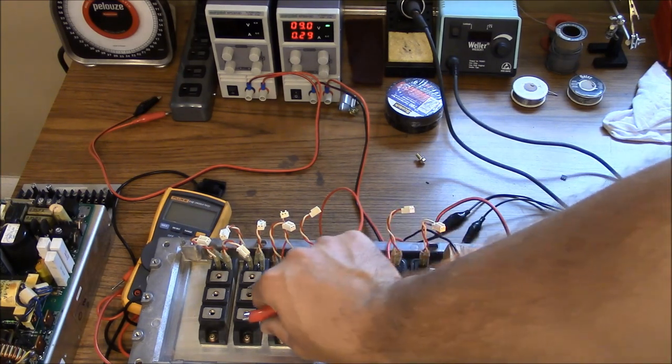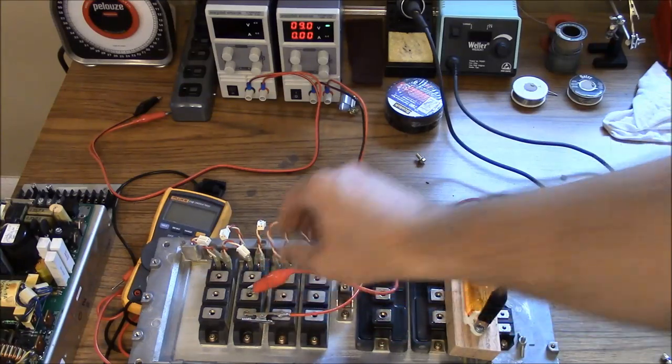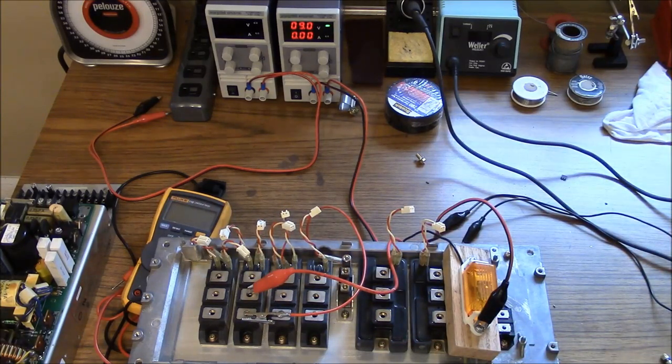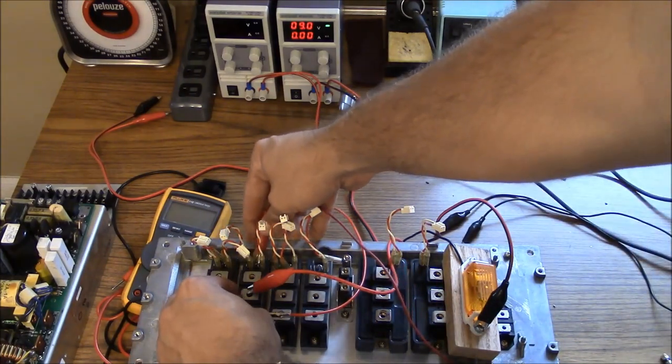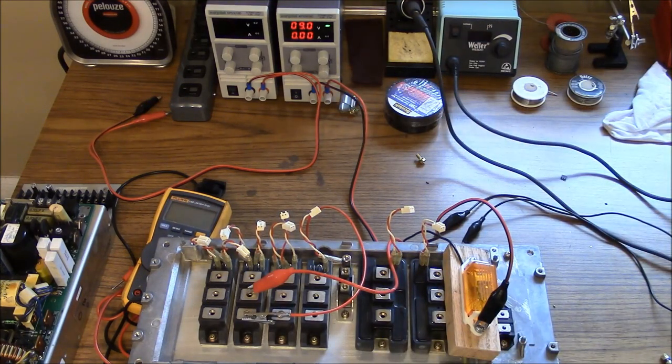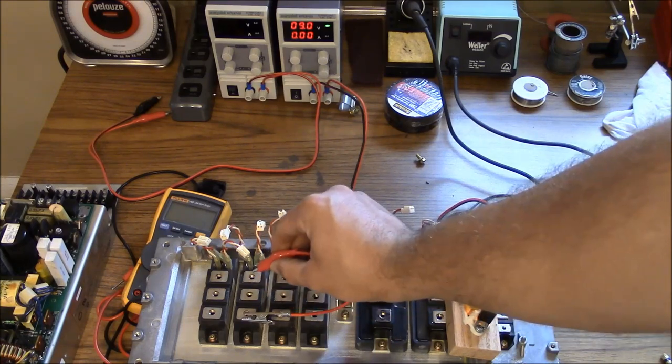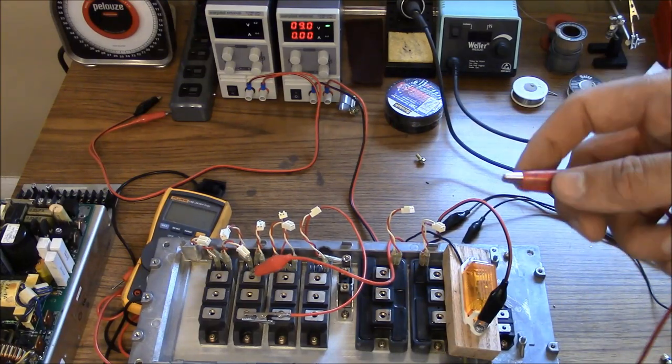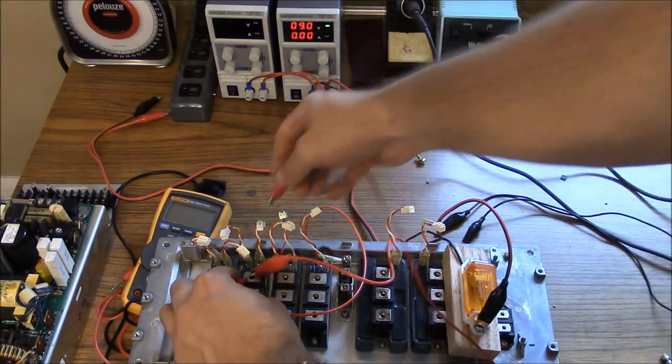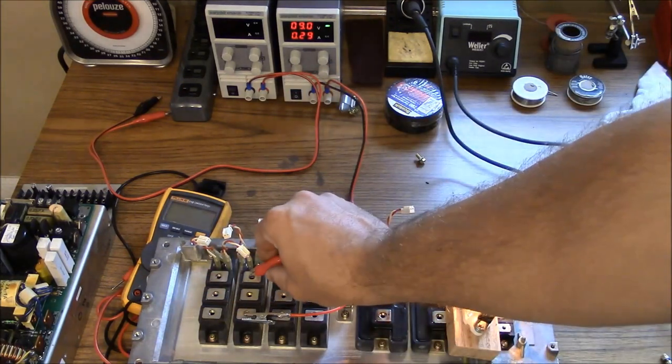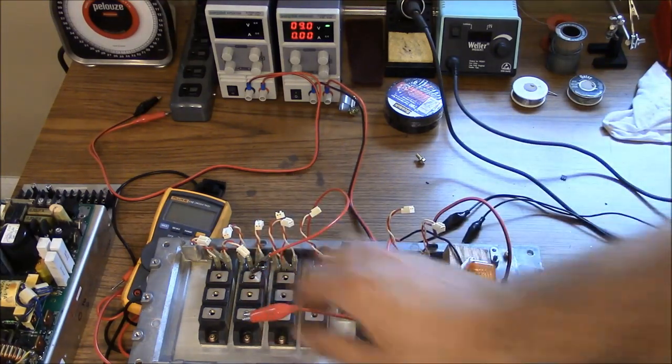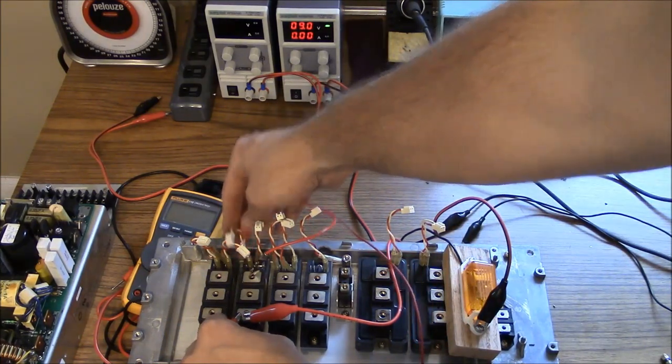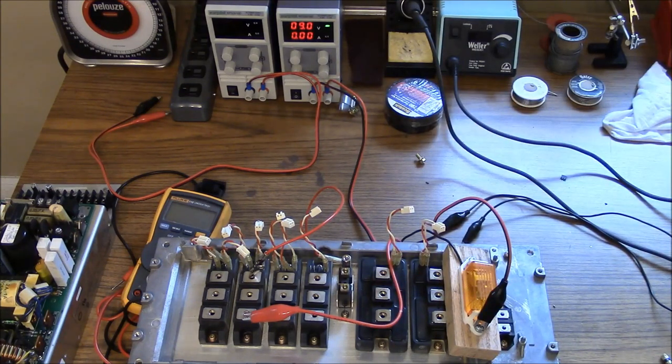Now if we reverse the circuit, so now we have the incoming power coming on the opposite side of the diode. And again we apply voltage to the gate - nothing happens. So that one is working correctly. Now let's test the other one, the other side of the diode, or the other side of the wave I should say. So if we connect the power from here to the other gate, again the circuit works correctly. And then if we reverse it like so and apply power to the gate, nothing. So this module is working correctly. Let me show you one that doesn't work correctly.